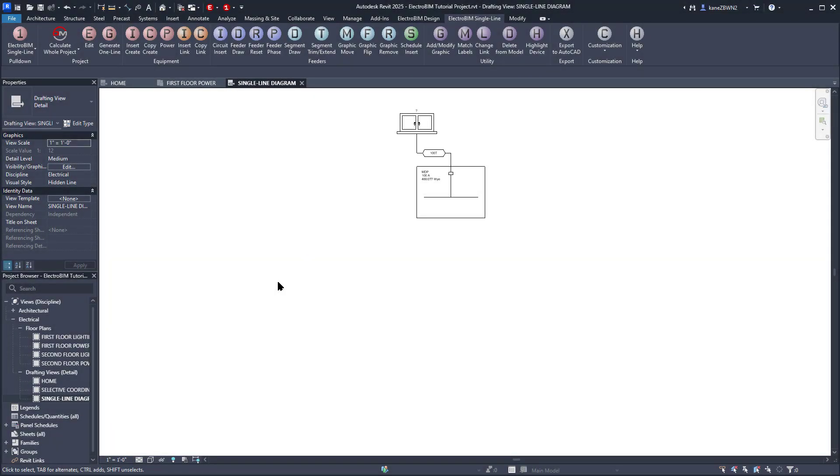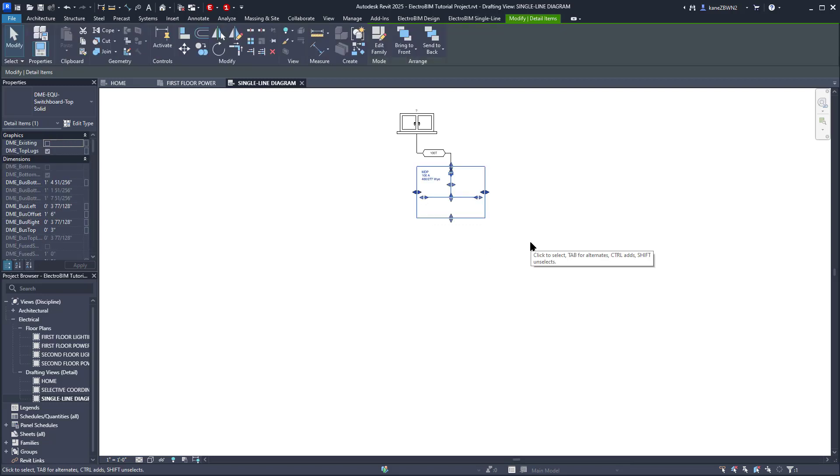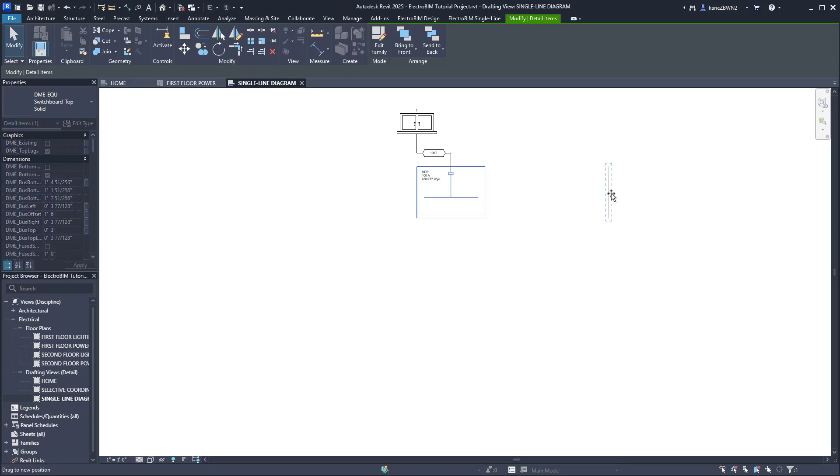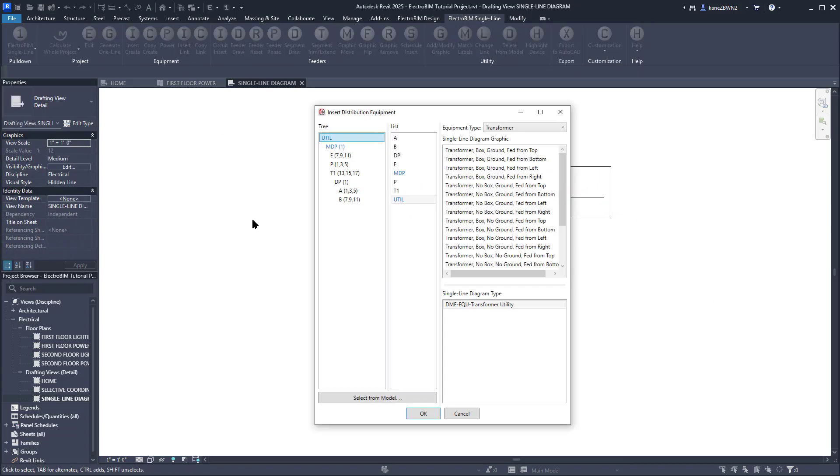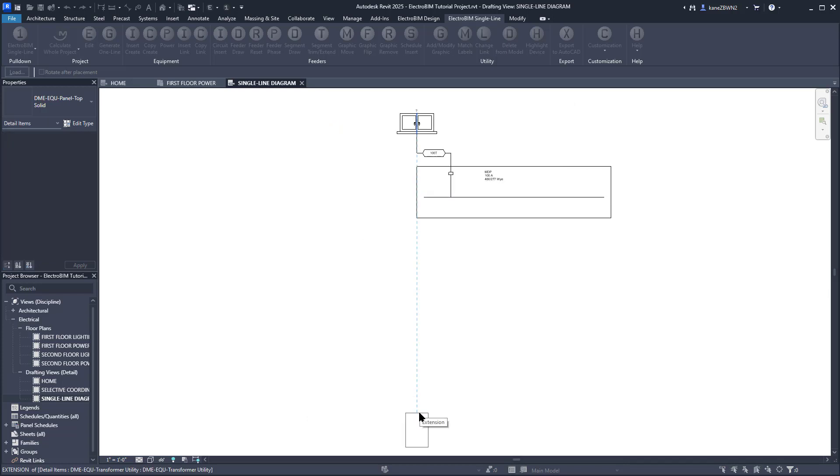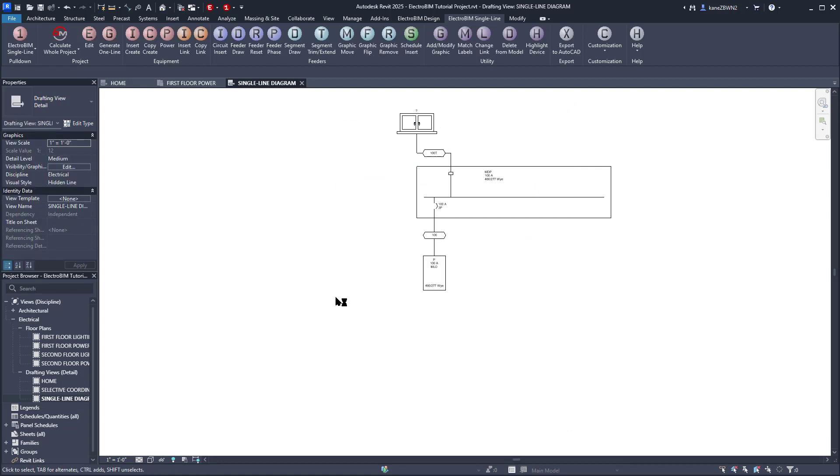We'll need to make room to draw the downstream feeders on this, so we'll just select the graphic. Then use this grip on the right to stretch everything out. Run Insert Link again, select Panel P, stick with the default graphic, press OK, and insert it under MDP. Again, the feeder is drawn automatically. I'm pretty happy with how this looks, so for the next panel, let's instead run the Copy Link command.